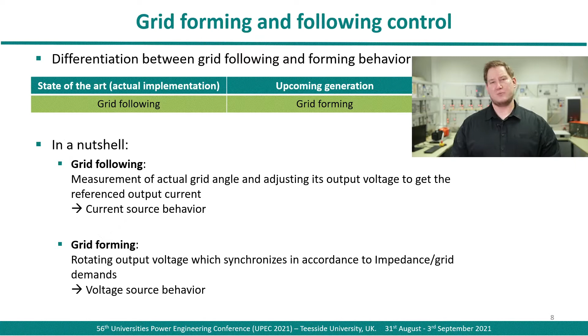To be mentioned, not all inverters have to be grid forming controlled, as long as the main properties of the grid will be maintained. Grid following means it measures the actual grid angle and adjusts its output voltage to achieve the reference currents. So, as the name says, it follows the grid. In other words, it will act like a current source. Grid forming control has to have a self-contained rotating voltage source which will just synchronize to the actual grid situation. There are two main requirements for the grid forming control scheme. First, it should behave like an ideal voltage source with an internal impedance. Second, it should have an inherent response to changes in the grid. So, it provides the highly required inertia while substituting synchronous generators with inverter-fed energy sources.